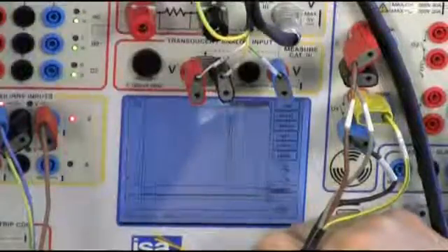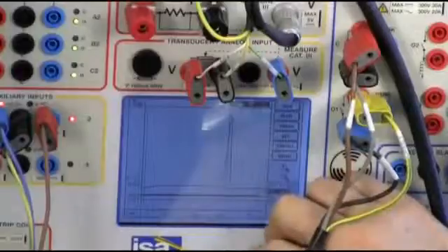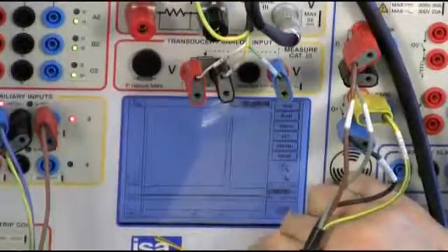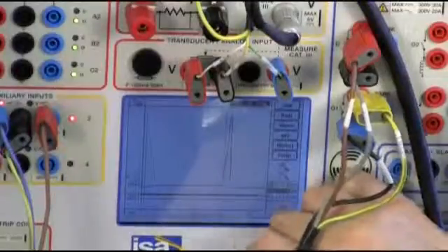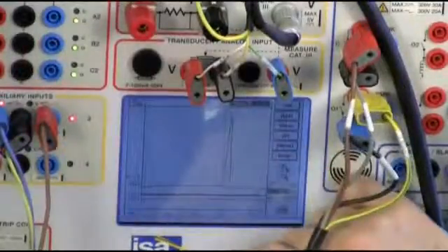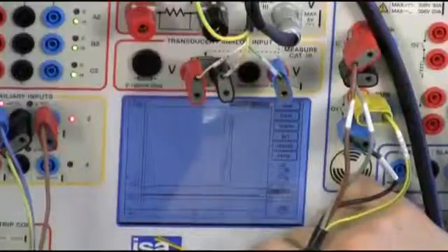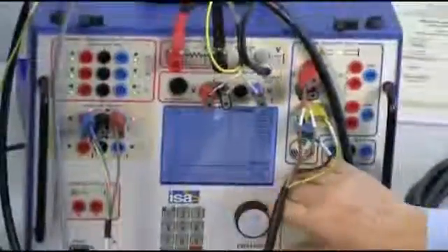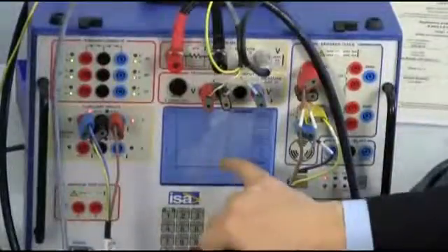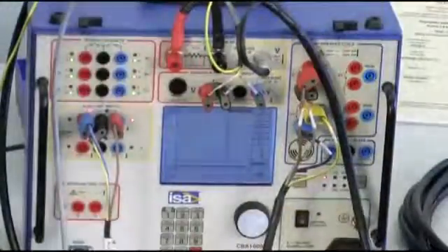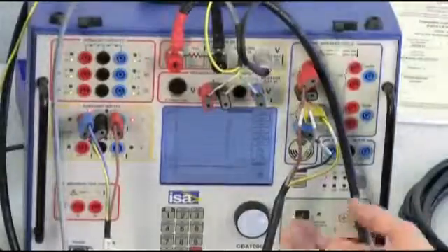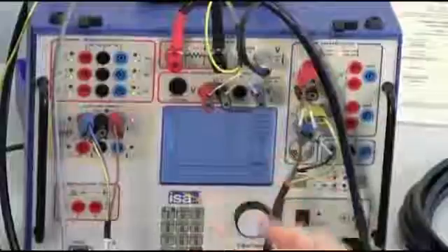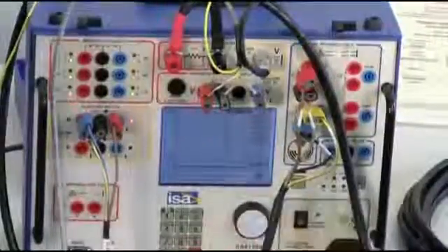You see? We are passing from micro ohm to more than 1 milliohm. But you can see that we have here 1, 2, 3, 4, 5 milliohm before the final opening. And this can be telling you that something is wrong or it is correct. Actually now it is correct.